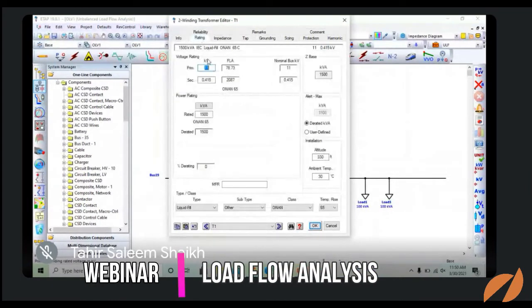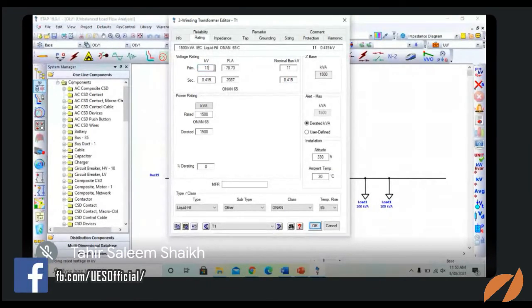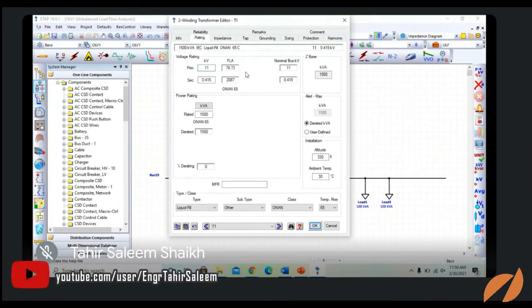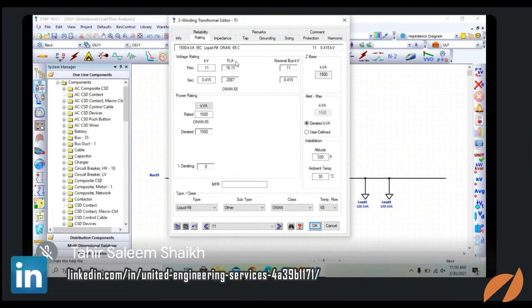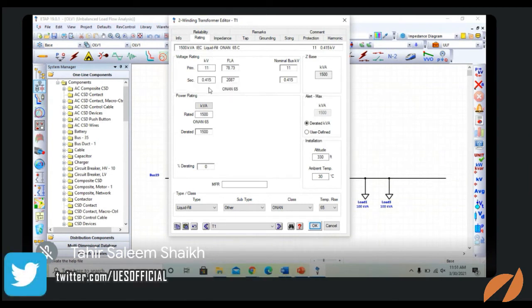Okay, now rating. The primary is rated over here. The full load amperage it will calculate itself. For example, if I put 12 kV, it will change the full load ampere. If I have 11 kV, it will give you 78.73 full load ampere. This FLA refers to full load amperage. Now for the secondary, I have rated it 0.415 kilovolt, which is automatically 415 volt, and the full load amperage is 2087.